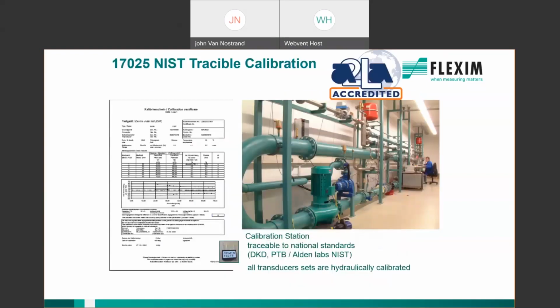I mentioned that we do calibrate every pair of transducers. Calibration is important. Our transducers are calibrated in a NIST traceable lab and under 17025 standards, and every meter gets a wet flow NIST traceable calibration to ensure that it's going to be plus or minus 1% in your application. So that's what you can expect taking a meter out of the box and putting it on your pipe from FLEXIM: plus or minus 1% with a repeatability of plus or minus 0.15%.